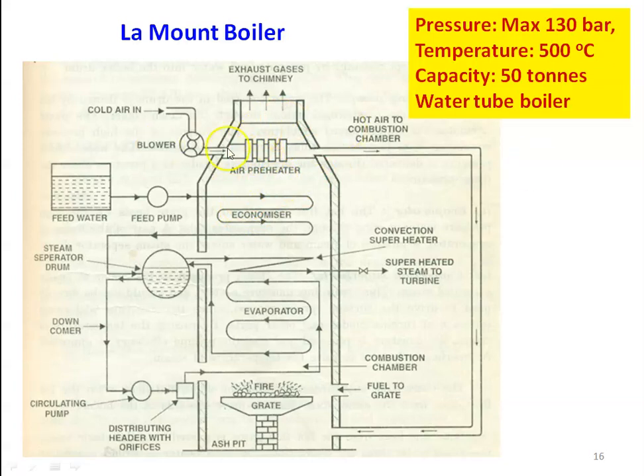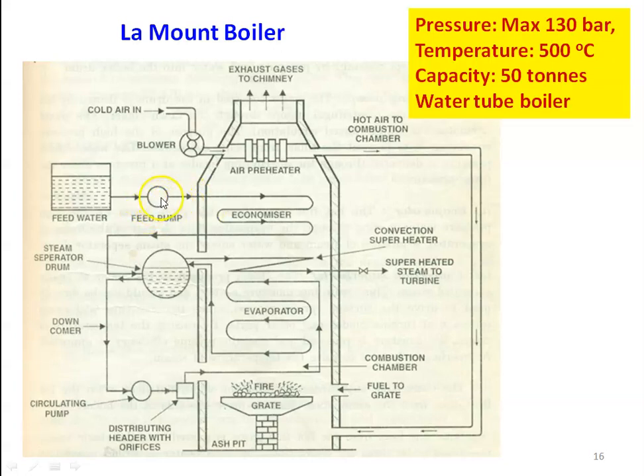Then the gases flow across the air preheater, where the air required for combustion absorbs the heat from the hot gases. After that, the waste gases leave to the atmosphere. Looking at the drum on the left side, we have the feed water tank. Through the feed water tank, using the feed pump, pressurized water is supplied — first flowing through the economizer, which utilizes the waste heat of the flue gases. If there were no economizer, the water would be admitted at room temperature. Using the waste heat in the economizer, the water is heated and enters the steam separating drum at a higher temperature, reducing the heat required in the evaporator. The economizer is an accessory installed to improve the efficiency of the boiler plant.